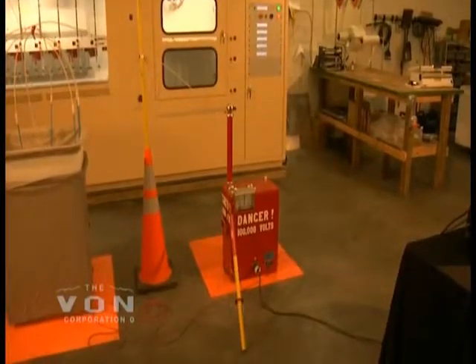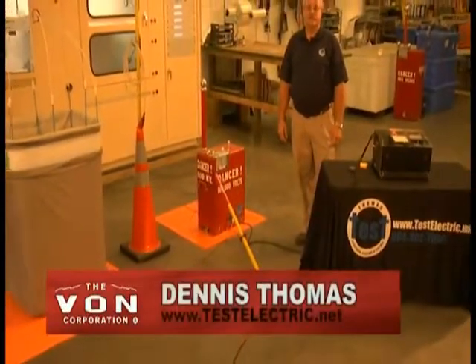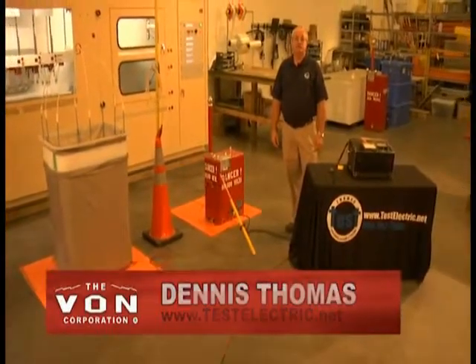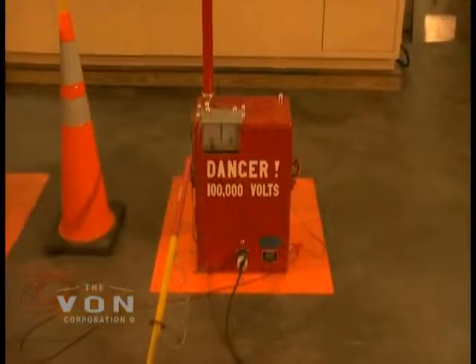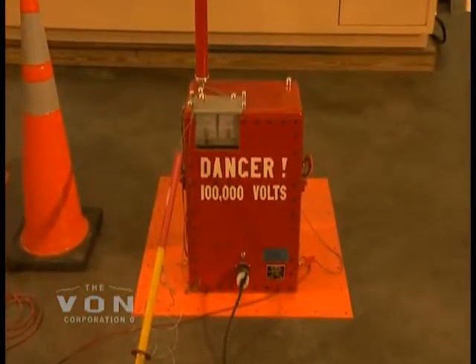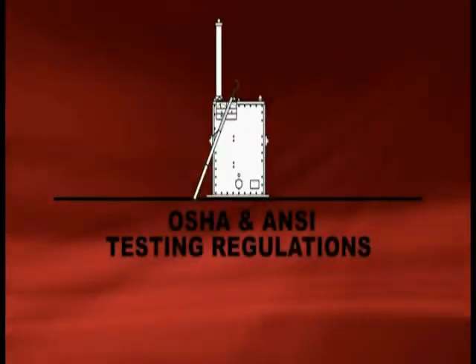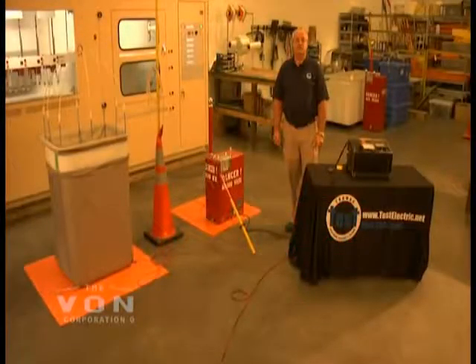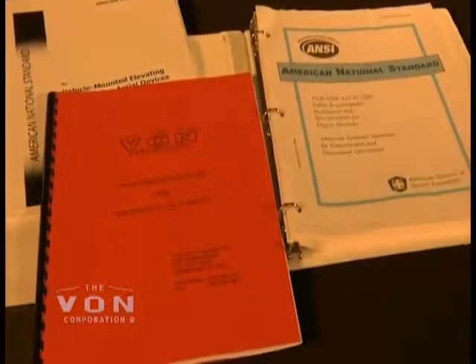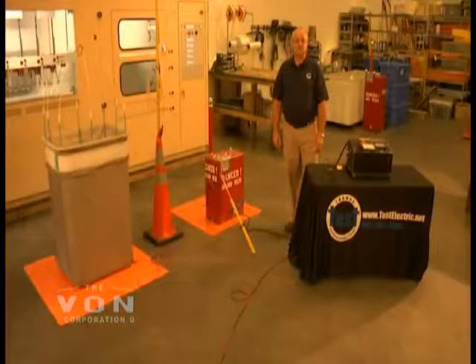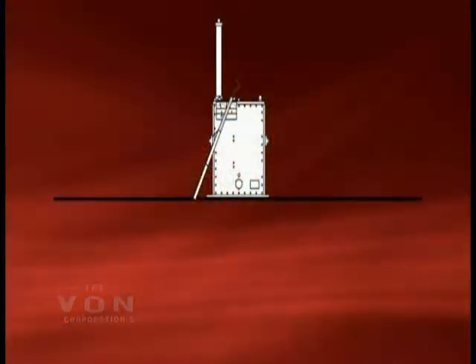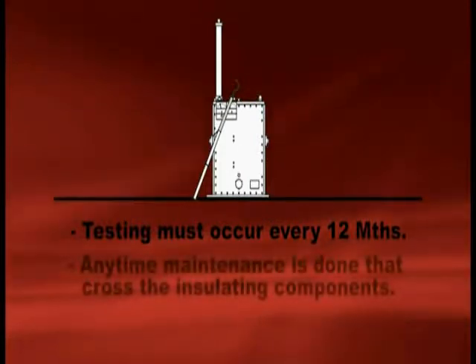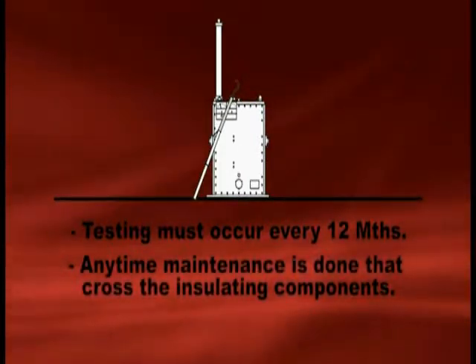Today we're going to go over testing a bucket truck, digger derrick truck, and bucket liner using the Von Corporation's C1 test unit. To start off with, what mandates us to test bucket trucks is OSHA 1926.453. OSHA regulations require that you conform to ANSI A92.2 standards. ANSI standards state that you are to test your units on a periodic basis of no more than a 12-month period, and anytime your unit has maintenance work performed on it that may cross the insulating components of that unit, that may bridge the upper boom or the lower boom.